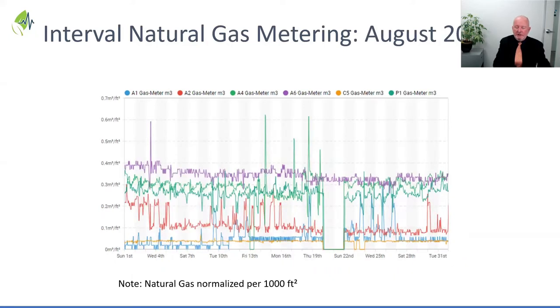The same applies during the middle of summer. Now if you look on the vertical scale there, these are much smaller numbers, but look at the dramatic difference between A1, the blue, and the rest. And I would tell you from our experience that the lion's share of that difference is entirely to be found within simultaneous heating and cooling. So it's your boiler plant running to reheat the air that you've already spent money cooling down with your cooling plant. Simultaneous heating and cooling - it's unavoidable in hospitals for humidity control, but if it's not controlled effectively through scheduling and temperature reset on supply air and all those good things, the numbers can become massive really, really quickly, and it's by far the biggest single opportunity.